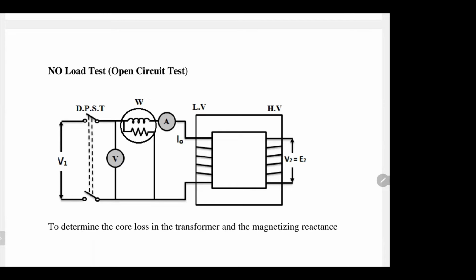So that's number one. Where should we perform the test? Low voltage side or high voltage side? Either one is correct, but there are recommendations. The recommendation is that the voltage should be applied to the low voltage winding. As you see here in this diagram, that's the low voltage side, and that's the high voltage side to the right. You open the circuit at the high voltage side and apply the voltage at the low voltage side and put all the measuring instruments on that side.